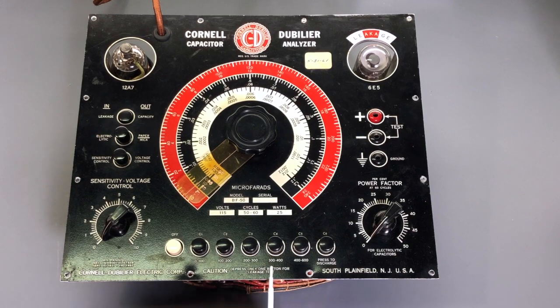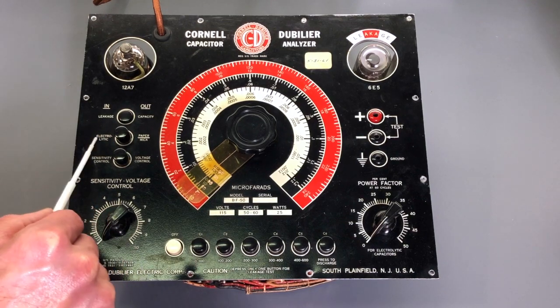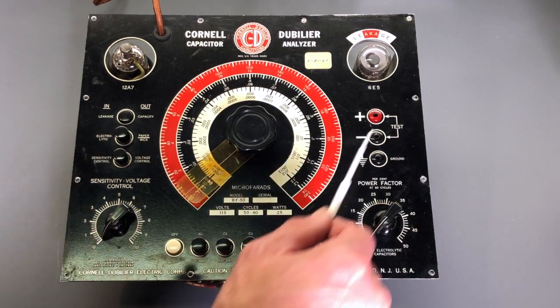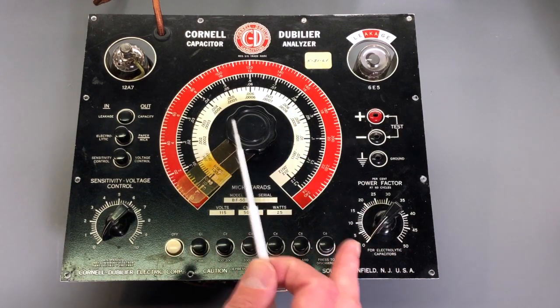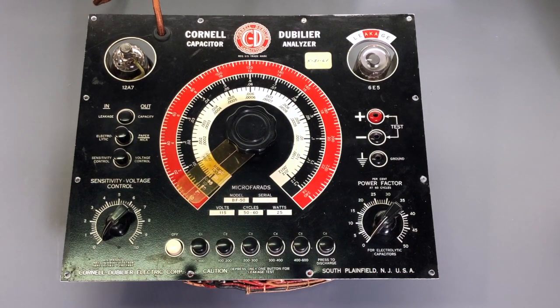So again, these voltages are related to the leakage test and the electrolytic mode. So we'll actually do that test first just to see if the circuitry is working correctly on those ranges. So I'll reposition the tester and the meter and power it up, and we'll see if the output voltage is correct.